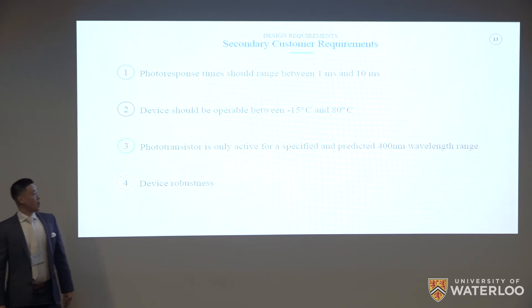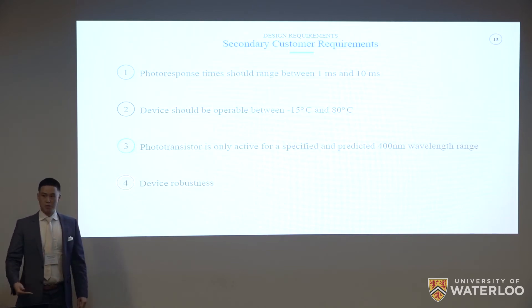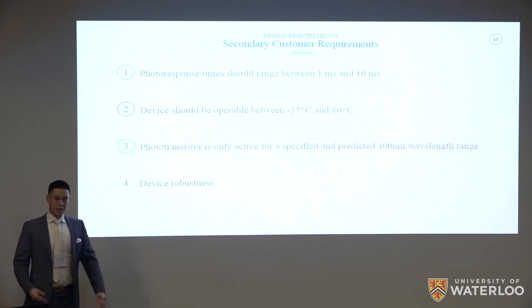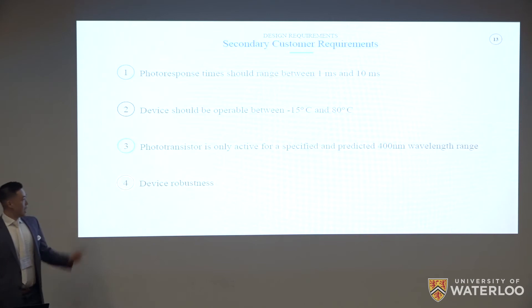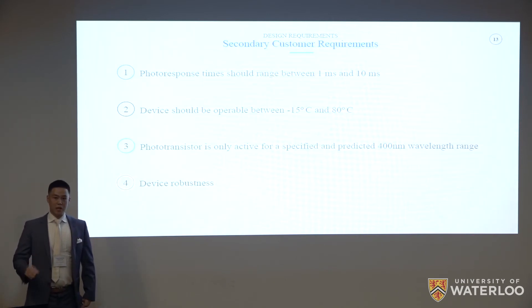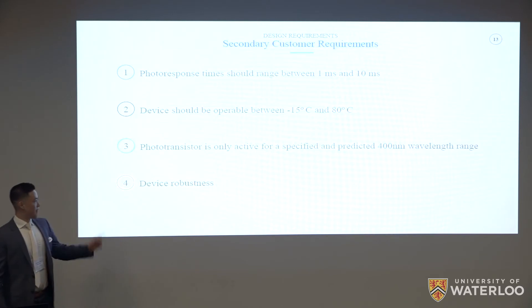For secondary requirements: photo response time should be between one and ten milliseconds, which determines whether the device can support live imaging or surgical use. The device must be operable between negative 15 and 80 degrees Celsius, consistent with what's currently on the market. The transistor should only be active for a specified and predicted wavelength — you want to detect what you intend to detect, not just any light. Finally, the device should be robust.